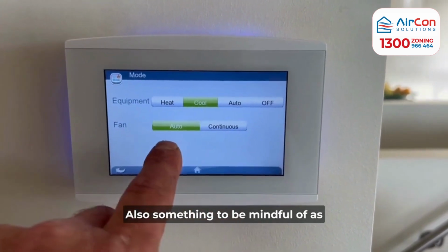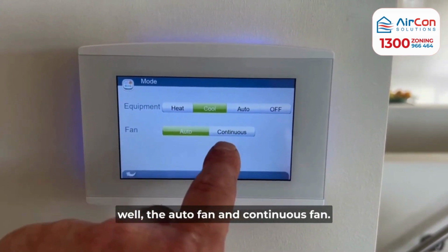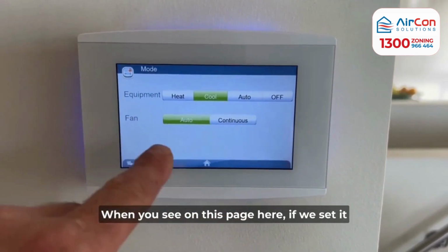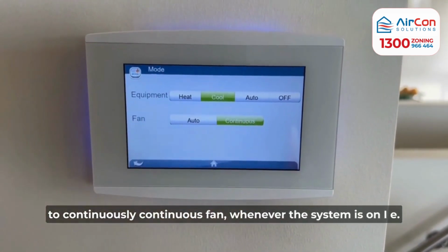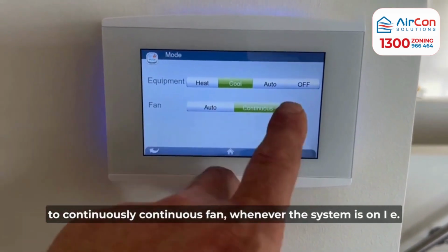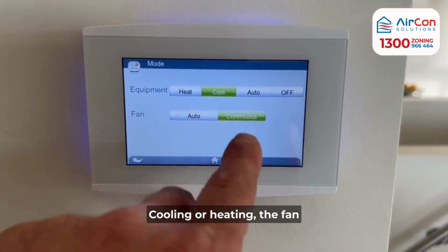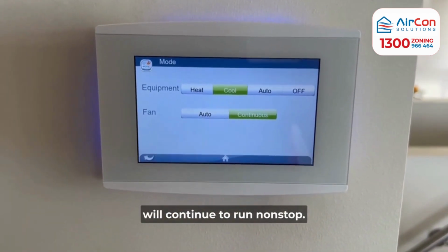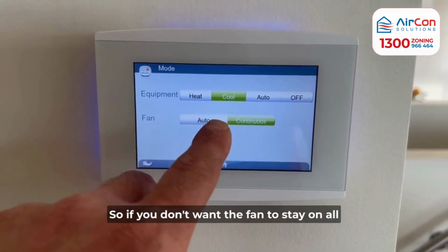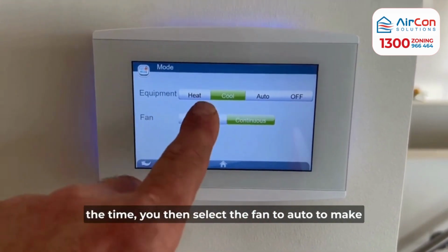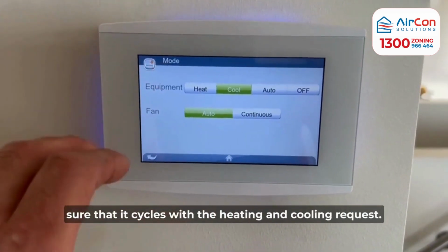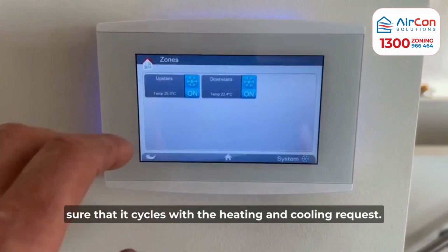Also, something to be mindful of as well, the auto fan and continuous fan. When you see on this page here, if we set it to continuous fan, whenever the system is on, i.e. cooling or heating, the fan will continue to run non-stop. So if you don't want the fan to stay on all the time, you then select the fan to auto to make sure that it cycles with the heating and cooling request.